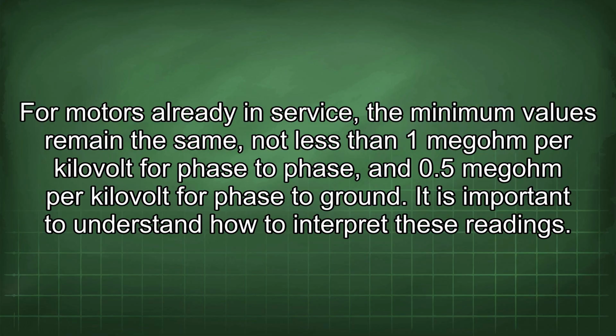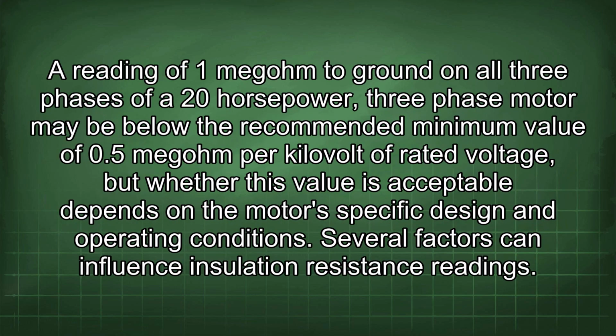It is important to understand how to interpret these readings. A reading of 1 megohm to ground on all three phases of a 20 horsepower, three-phase motor may be below the recommended minimum value of 0.5 megohm per kilovolt of rated voltage, but whether this value is acceptable depends on the motor's specific design and operating conditions.